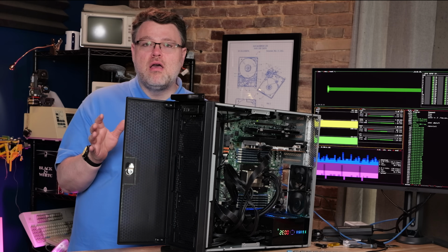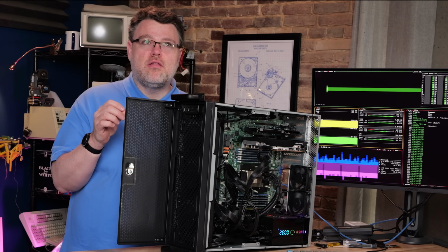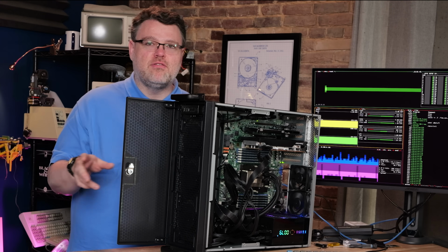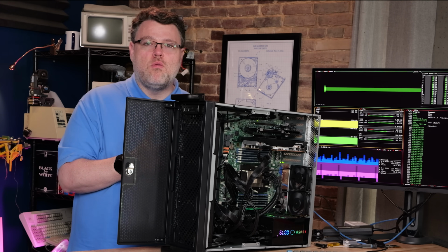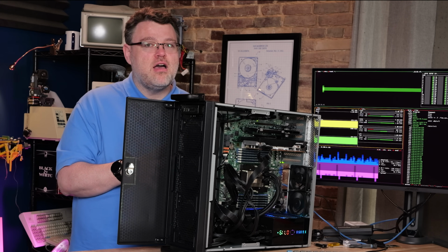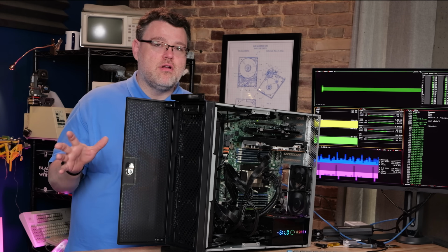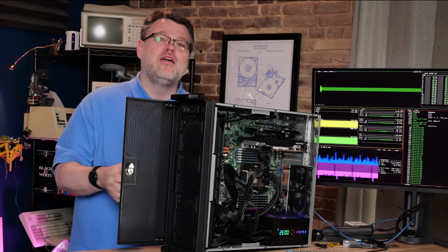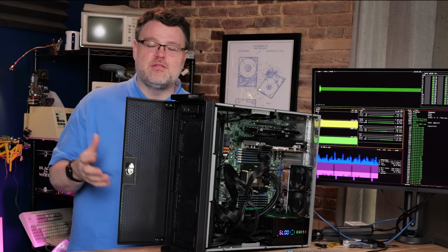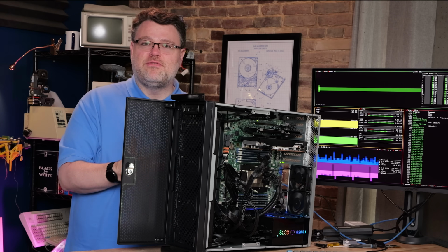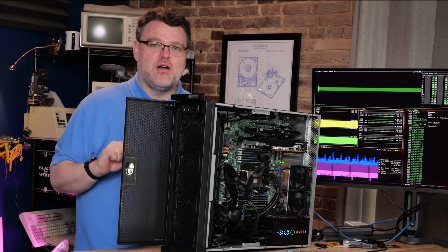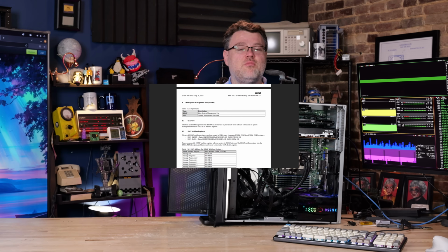I had a problem a couple of months ago where the backup generator for the data center could not keep up with grid mains, and so the data center was looking for a way to not take the jobs completely offline, but reduce the amount of power that the systems were using, because it was borderline, and this would have been perfect. So I'm glad that we have a solution now for this sort of thing, because I can just tell all the machines in the fleet, hey, you use 200 watts now instead of 400 watts, and that's a pretty good stopgap.